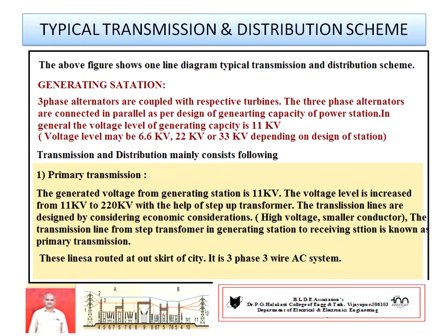Number one: primary transmission. The generated voltage from the generating station is 11 kV, which is then boosted to 220 kV. Electrical power is then transmitted on three-phase transmission lines at 220 kV, because the voltage is increased in the generating station itself by a step-up transformer. This 220 kV is routed on transmission lines whose towers exist on the outskirts of the city. These lines run from the generating station to the receiving station, and are called primary transmission lines. These are generally a three-phase, three-wire system.